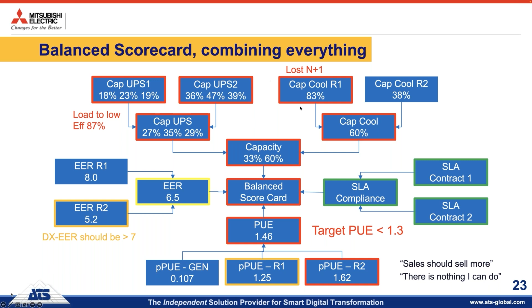So that's what I did. I moved part of the equipment from room 1 to room 2. You can see I got my N+1 back, so I have my redundancy back. But in the meantime, my EER of this room has improved. So now my EER is even above 7. So just by moving IT, I improved my efficiency, I have my redundancy back, and I also have a big impact on my PUE. Because if a CRAC unit's load is going down, in general, efficiency is increasing. So I'm just slightly above 1.3, quite close.